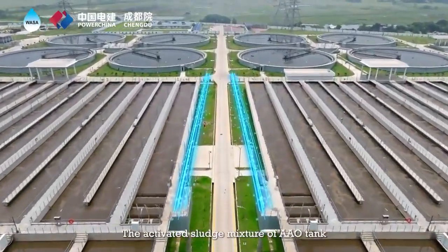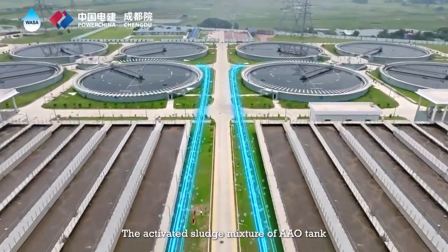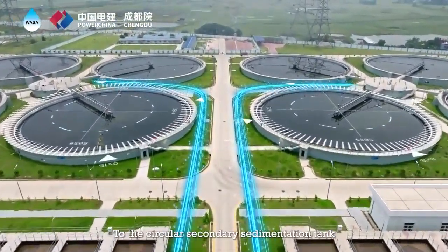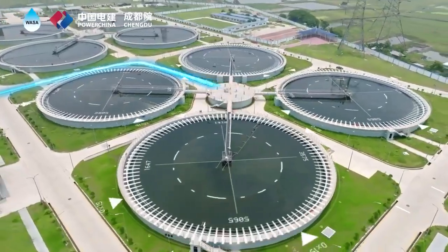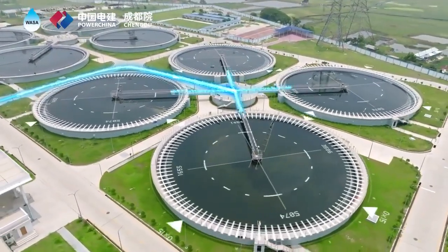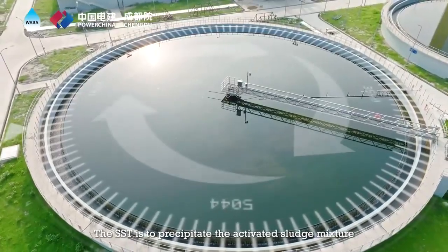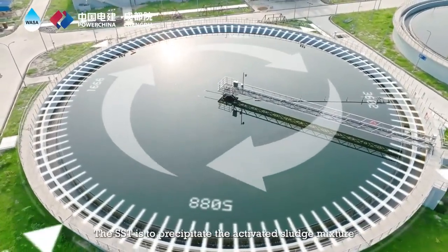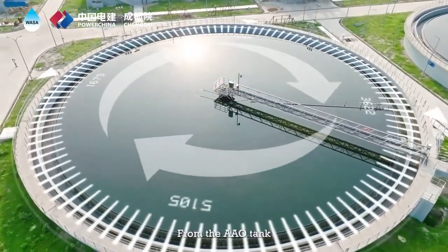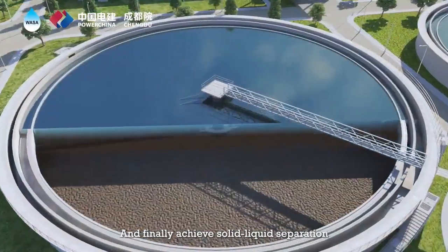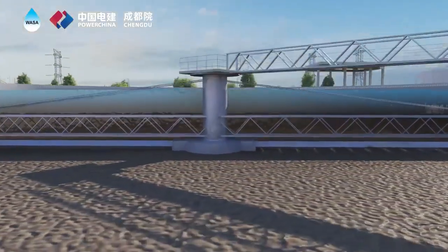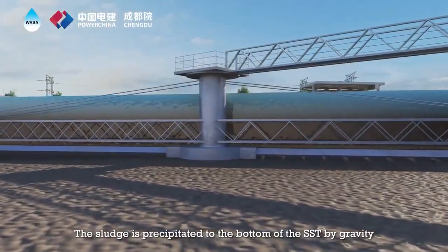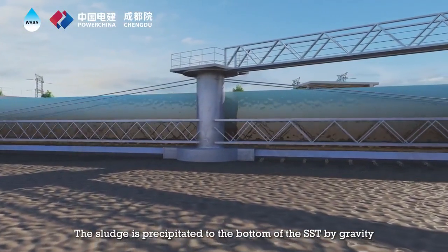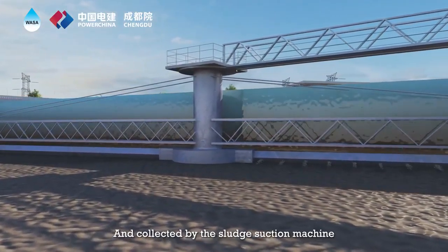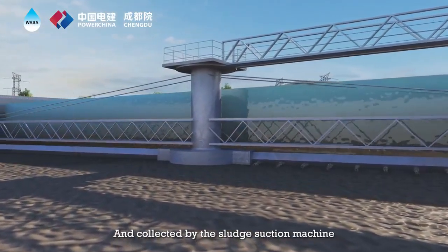The activated sludge mixture of AAO tank is evenly distributed to the circular secondary sedimentation tank by equalization tank. The SST is to precipitate the activated sludge mixture from the AAO tank and finally achieve solid-liquid separation. The sludge is precipitated to the bottom of the SST by gravity and collected by the sludge suction machine.